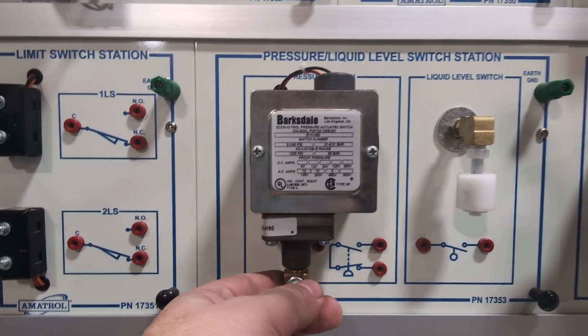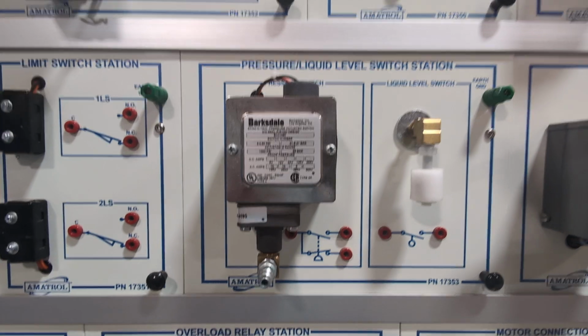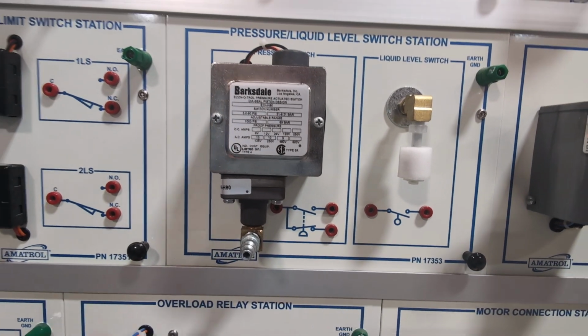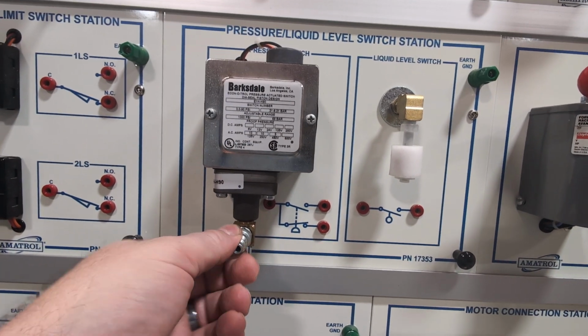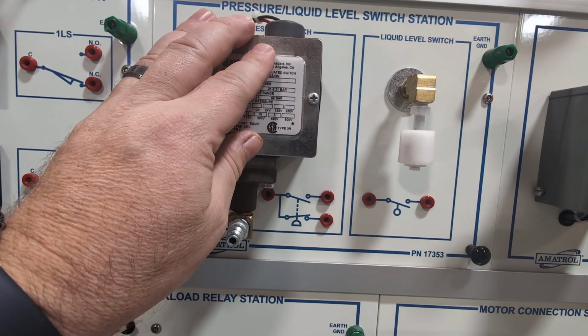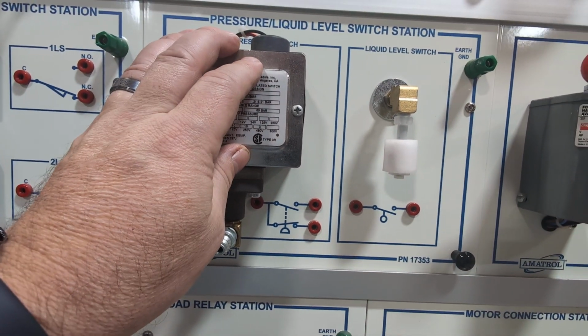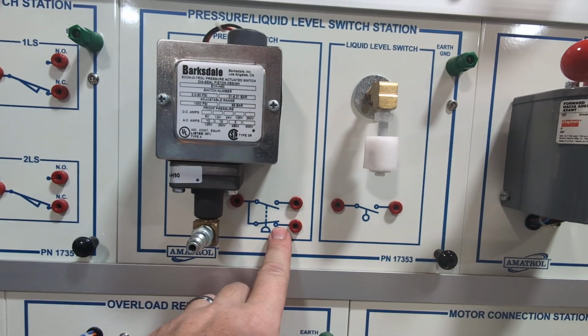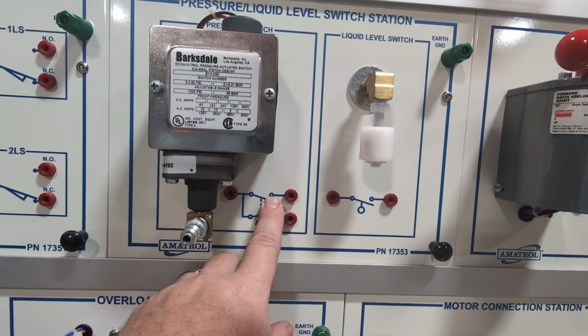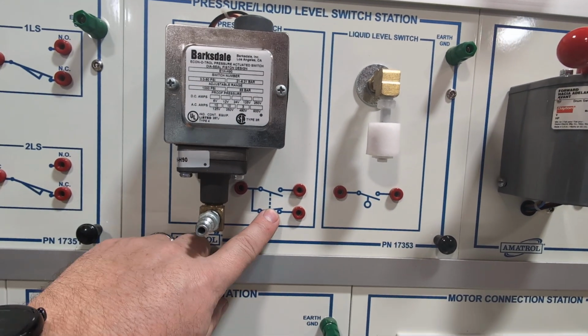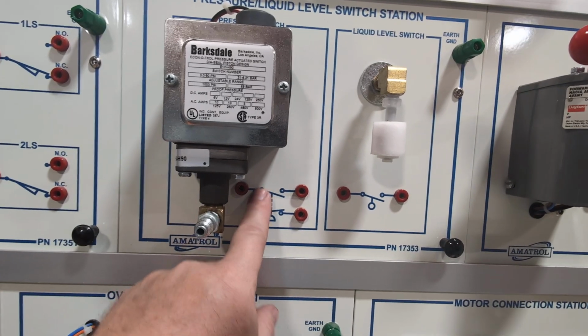What happens is I apply this to air pressure. Machines where I used to work need 80 pounds. So I set this up for, let's say, give or take 10%. I set it up for this. So if I don't have the 80 pounds, it's not going to run. This is the switch, normally closed, normally open. So when it gets to 80 pounds, it comes off of this and activates this.